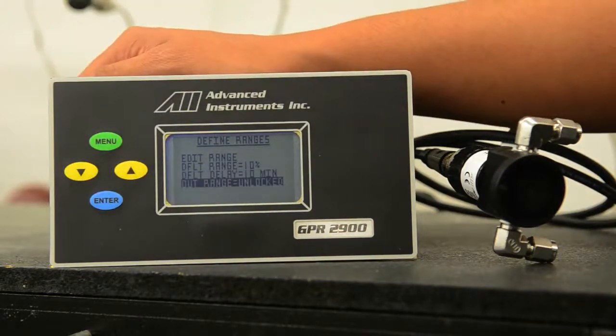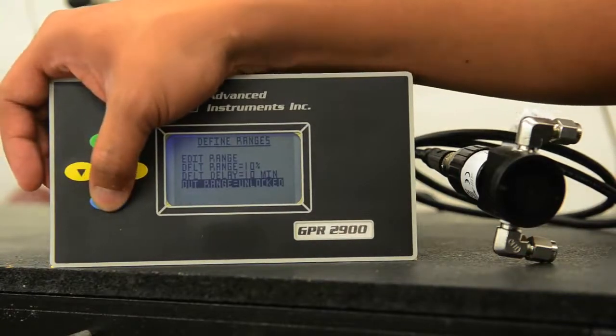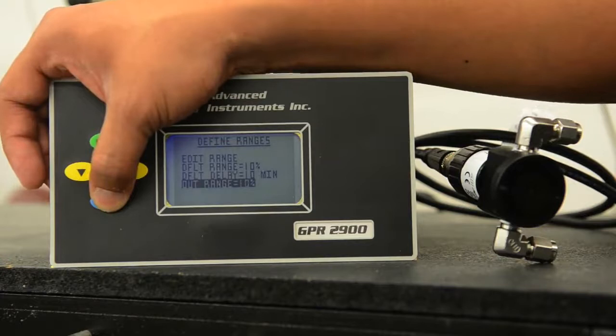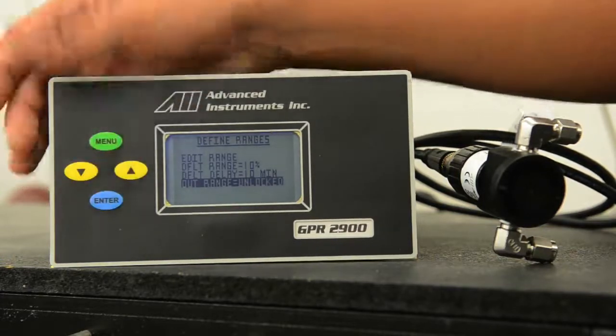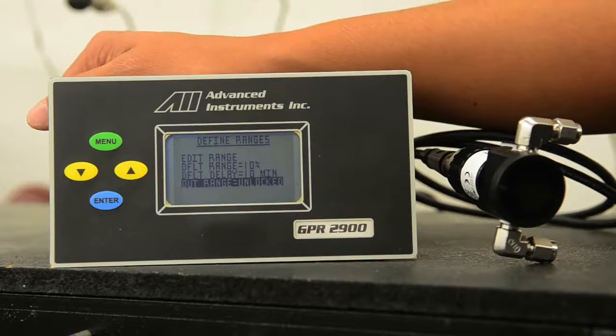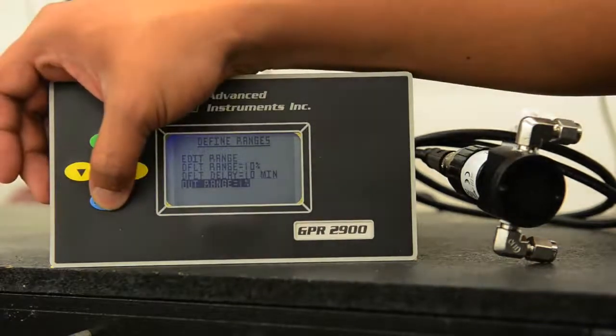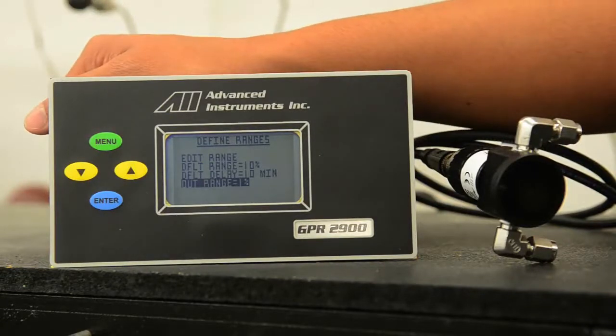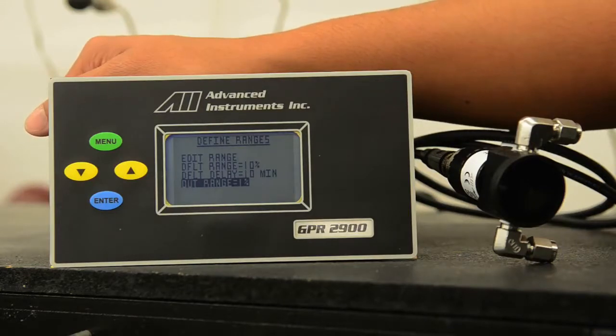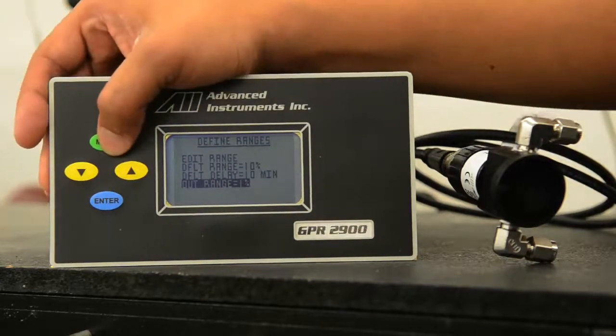You also have the out range option. This is your output range option, and if you select enter, it scrolls through the ranges that are with the analyzer, and currently it is unlocked. That means your 4 to 20 output will stay at whatever current range you're in right now. If you would like to lock that range in to, say, 1%, your 4 to 20 will always be at the 0 to 1% range, regardless of what the screen is showing. This is ideal if you have alarms set off your 4 to 20 and you would not like to trigger those alarms when doing calibration or just regular maintenance on the analyzer.